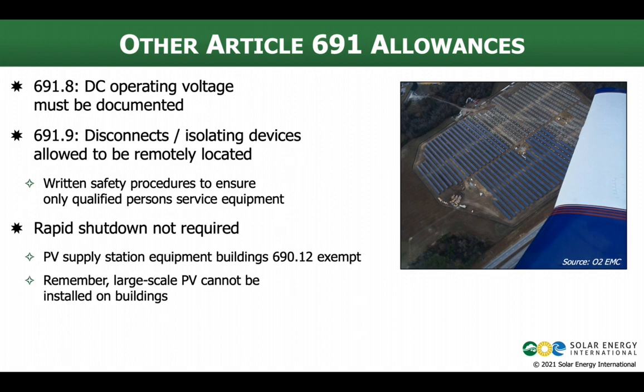Rapid shutdown is required. Of course it's not, right? These systems can't be on buildings. Rapid shutdown is for systems on buildings. There is also an exemption for PV supply station equipment buildings. So you may have buildings that are part of a large-scale PV system. They could be housing power electronics. They could be housing other equipment that's part of the system. Those as well are exempted from the rapid shutdown requirements.